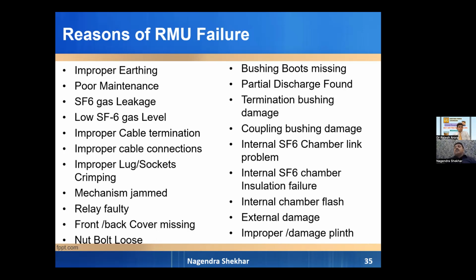Relays are faulty, back covers are stolen or gone missing, boots of bushings are missing, partial discharge found because of any reasons, termination bushings are damaged. Coupling bushings, when two or more RMUs are coupled together, are damaged, or the gaskets at coupling fail, resulting in moisture ingress, leakage of SF6 from chamber, internal chamber insulation failure and other external damages. Improper or damaged plinth results in venting of RMU.